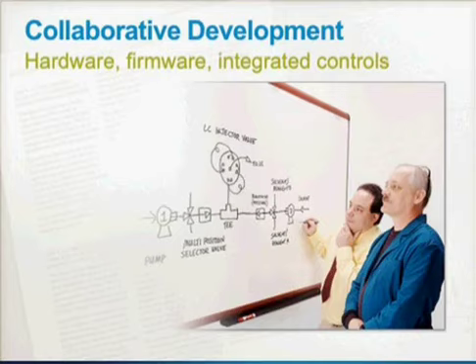Well, what we found when we first started the development of this concept was that we really had tight tolerances. We did not have a lot of room for error. So when we considered all the various other options out there, really all you had were two. You have an LC system where you swamp the flow out of the back end of the LC, so that if you've got an acidic solution coming through, if you crank up the volume flow rate high enough, you can remove all your problems. But, of course, then you definitely dilute your signal, and so that was anathema. We were not allowed to do that sort of thing. We tried then to apply this gradient concept that we talked about before, and we found that unless you had tolerances or precisions on the order of 0.1%, you just were not able to achieve the performance that we needed. We got wild pH swings outside of that tolerance range.